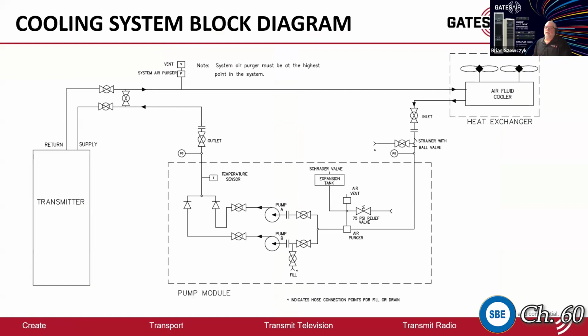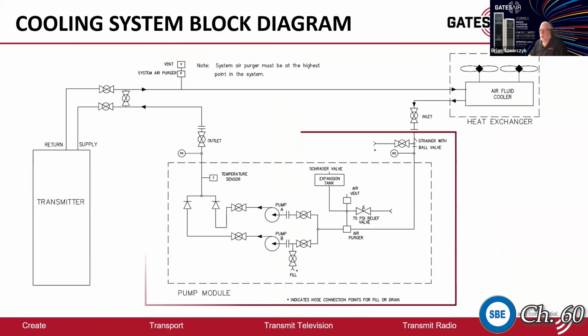So this is a schematic of a typical cooling setup. In addition to the transmitter, you're going to have this thing called a pump module. What the pump module does is it's responsible for circulating the coolant through the transmitter into the outdoor heat exchanger. And our pump modules are designed with two pumps in them. They run in parallel, as you can see. But a single pump will support the system.